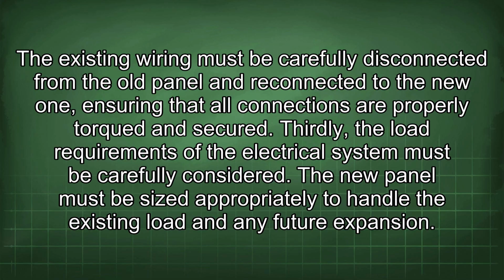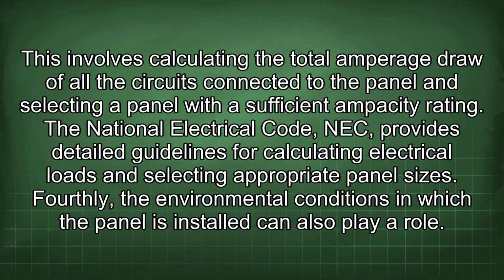Thirdly, the load requirements of the electrical system must be carefully considered. The new panel must be sized appropriately to handle the existing load and any future expansion. This involves calculating the total amperage draw of all the circuits connected to the panel and selecting a panel with a sufficient ampacity rating. The National Electrical Code (NEC) provides detailed guidelines for calculating electrical loads and selecting appropriate panel sizes.